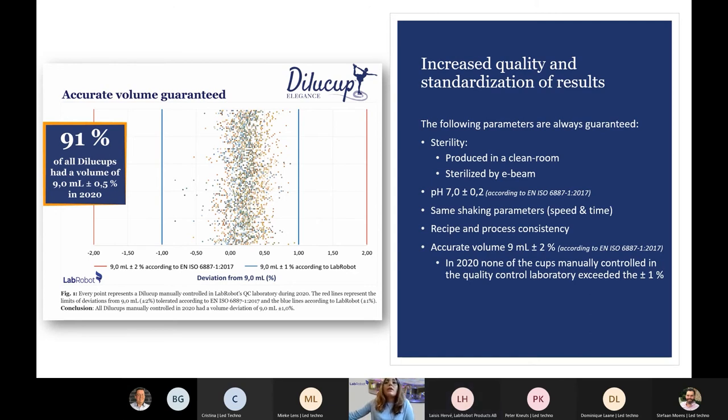The volume of Dilucup is highly accurate and is always within 9 ml ± 2%, according to ISO 6887. In an analysis I did in 2020 of all Dilucups manually controlled at the laboratory in LabRobot, every point represents a Dilucup. The red lines represent the ISO limits of ±2% deviation, while the blue lines represent LabRobot's tighter specification of ±1%. All Dilucups measured were between -1% and +1% deviation from 9 ml.